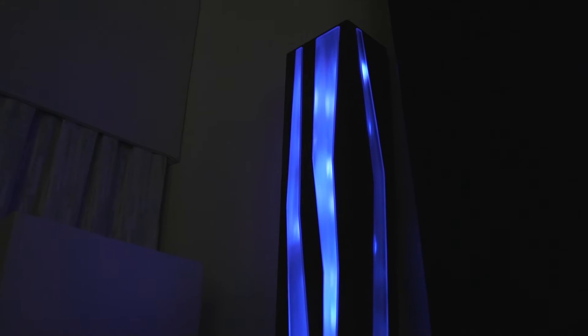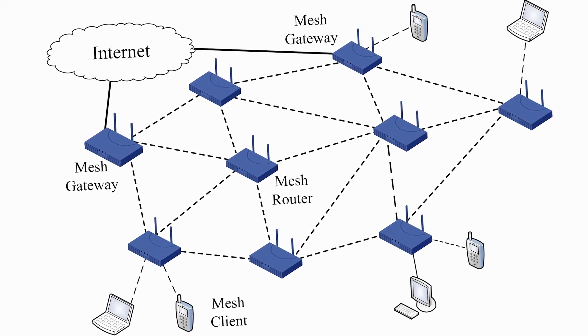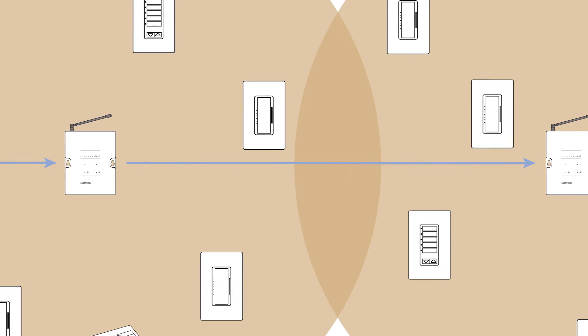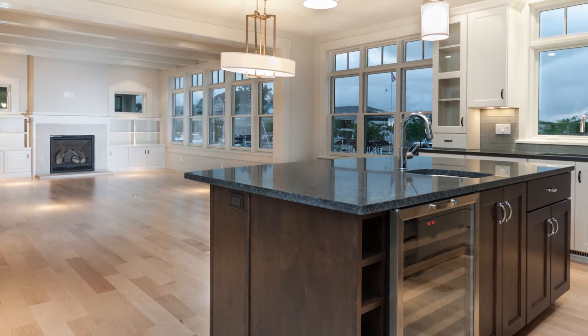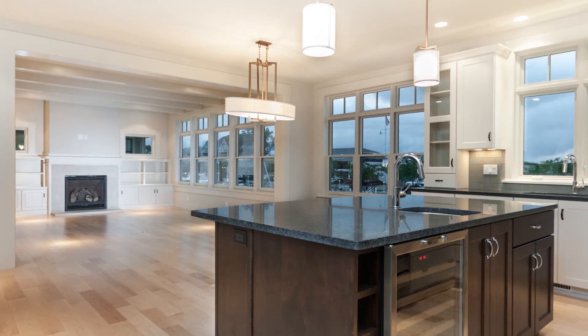This also makes it difficult to troubleshoot problems on the network. With a fixed network, the RF coverage and the route for these messages is constant. Unlike the mesh network, which utilizes different routes and devices each time, the fixed network is set up with dedicated sending, receiving, and computing stations in predetermined locations. This means messages, like turning the light on, are delivered over a predetermined route, providing a predictable, fast reaction time to a simple button press, regardless of that device's location on the network. The network is not shared or doing other work, so messages move up and down the fixed network very quickly.